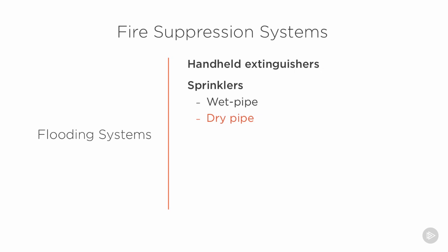As well as, of course, a wet pipe system is going to spray water much more quickly to a certain area than a dry pipe system. But many server rooms today use inert gases. Now, in the old days, we used halon. Halon 1301 and halon 1211 were the two main halon products. And halon was fantastic for putting out a fire, but killed people.